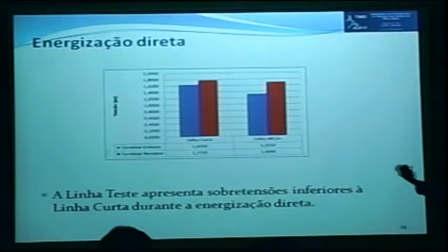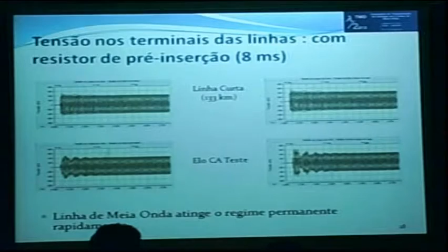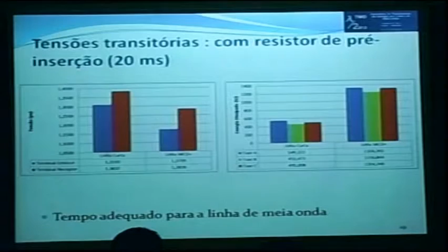This is the short line and our half-wavelength line. Here our transient is taking longer to disappear. And for the half-wavelength, it is damped immediately and it enters into the normal regime. In this case, we have pre-insertion circuit breakers for 20 milliseconds, which would be the proper time for the half-wavelength. So in the receiver end, we have a smaller disturbance. In compensation here, we have the energy from the pre-insertion circuit breaker.